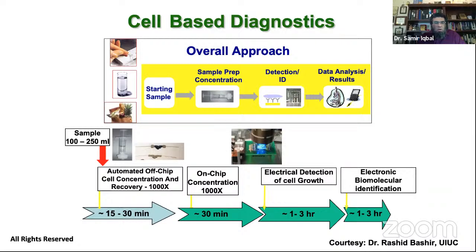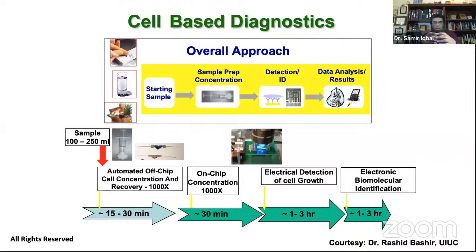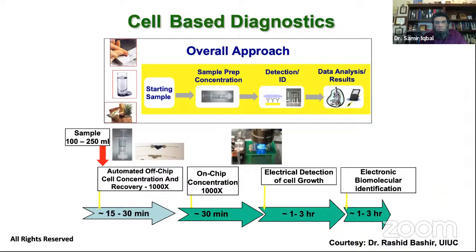When we take things to the lab-on-chip format, everything needs to be done at much smaller scale and much faster. We start with a small amount of material — maybe 100 to 250 mL — clean it, remove red blood cells or white blood cells depending on the application, and then on the chip do everything. You can see the objective lens and compare the area of the green holder, which is just a PCB — printed circuit board — with the lab-on-chip on top of it. This is where the heart of advancement is.